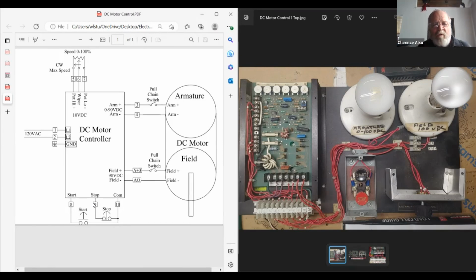Nathan, we were working with the armature voltage, and these are the three inputs we need for this to work. You need a speed source, you need power to it, and you have to ask it to come on. Any one of those things could have kept that from happening, and we could have been checking at terminal 5, 6, or 7, or right there on the pot leads.